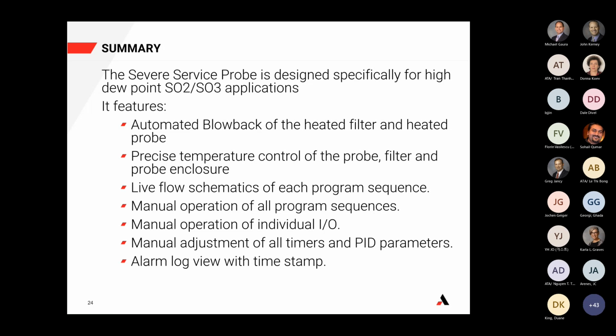And I think one of the biggest benefits for most customers is the alarm log view with the timestamp that tells you exactly what's going on, not only with the probe and the controller components, but also with your analyzer. It tells you if you're having problems there as well.